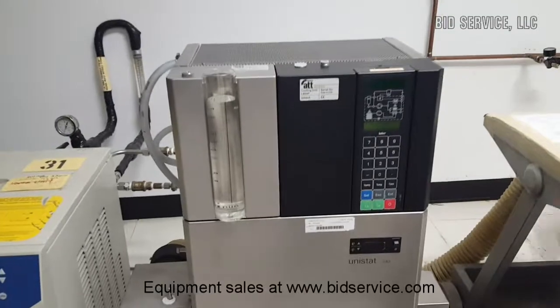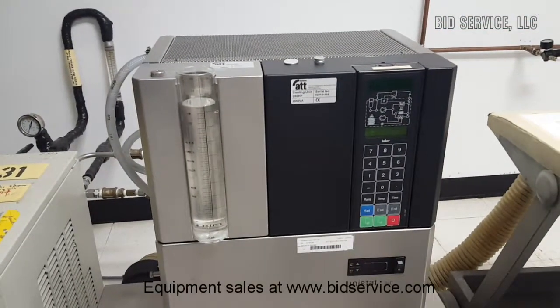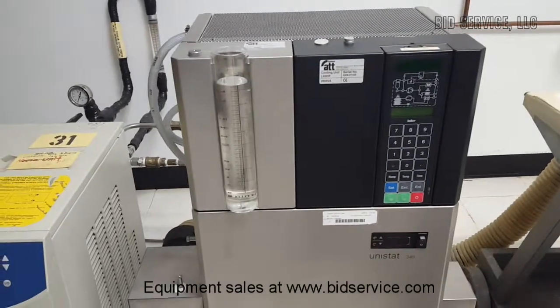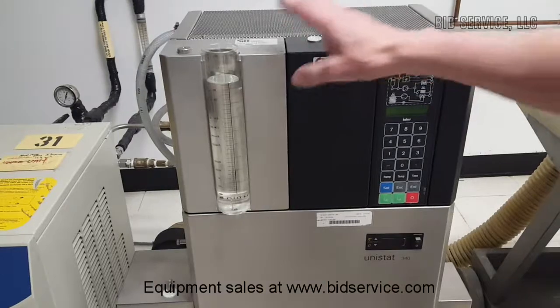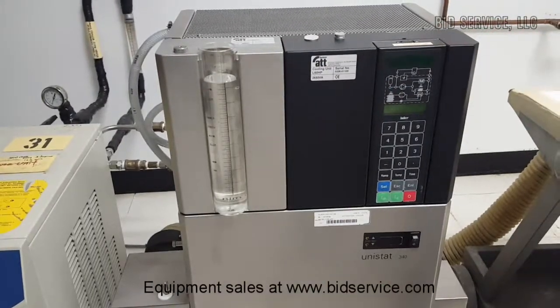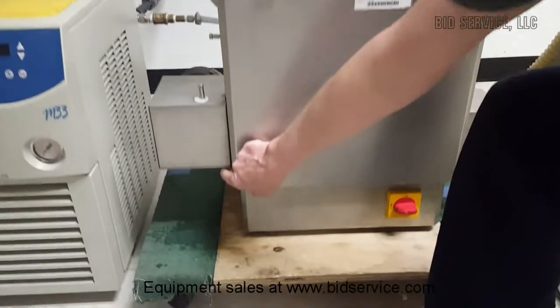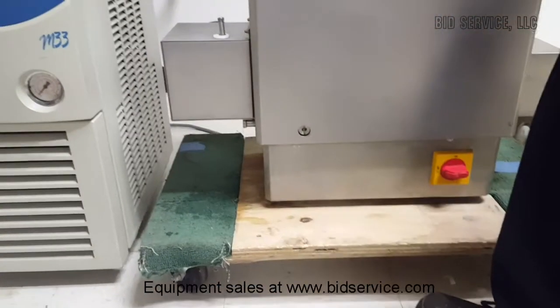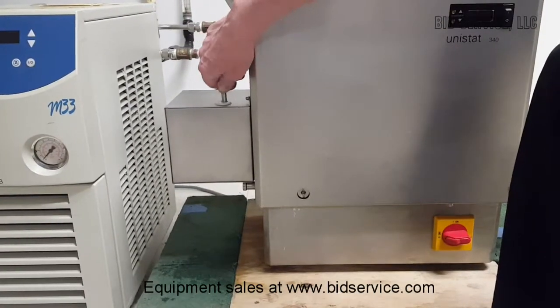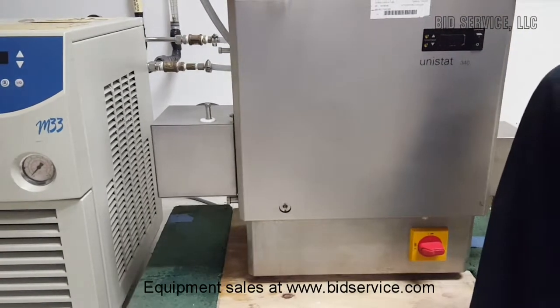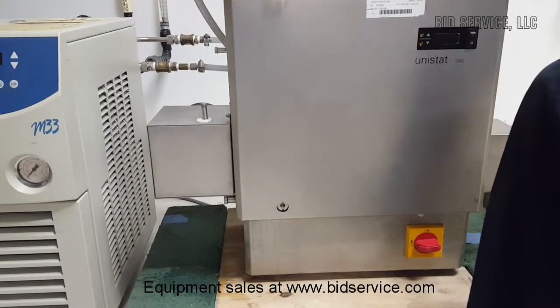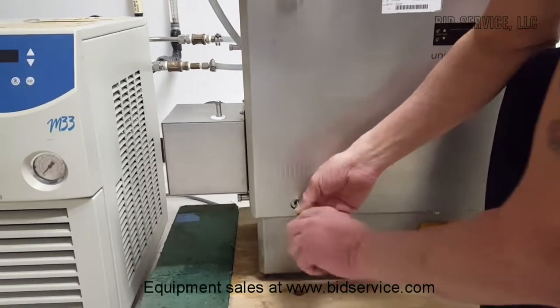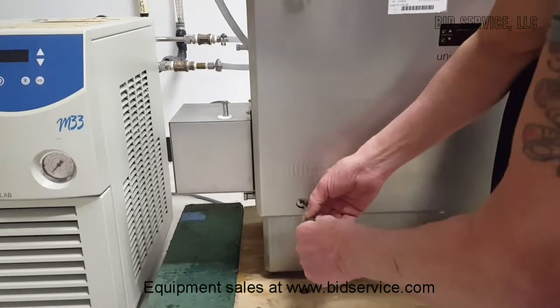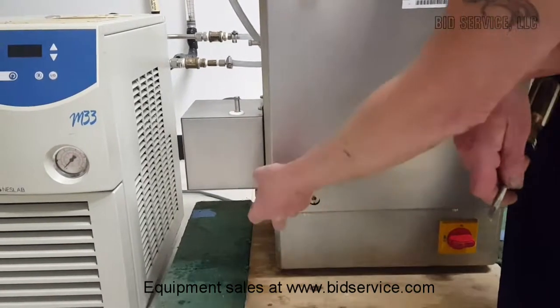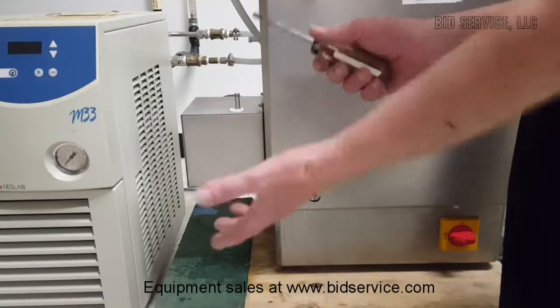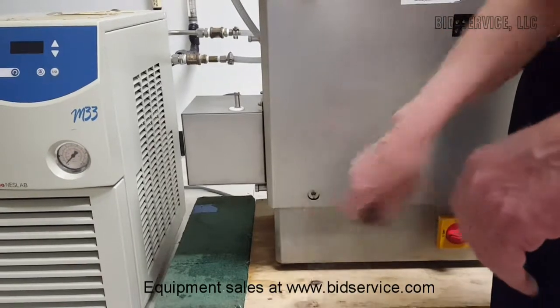Back now. I've completely drained the system and the hoses out of all alcohol, rinsed it out clean. We now have DI water in place. Before we start up, I just want to show you one feature down here that's very convenient. If you look down here, you'll see a drain plug. That drains the system. This is also a drain, and that's a drain as well. When you drain the system, I have found that especially with the thermal hoses, if you hang them up and you open this up, and then this is very convenient. This is a valve that you turn counterclockwise, and this will open the valve to this drain, so when you have to stop, it doesn't fly all over the place.